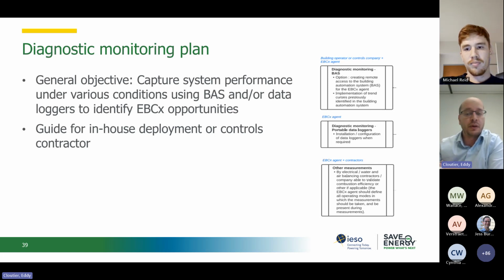When the control system has limits or measurement is needed for an element that is not controlled by the BAS, it may be necessary to use portable recording equipment, which still happens quite frequently, depending on what you want to measure. In certain cases, it's also necessary to hire a contractor to carry out some kind of measurement. An example of that would be efficiency of a boiler, so a combustion test. Another example, and it's always depending on what kind of equipment you have at your office or in your team, it might be necessary to hire a balancing contractor to measure airflow, water flow in some cases. So that's the type of measurement that usually is not always easy to do by yourself.